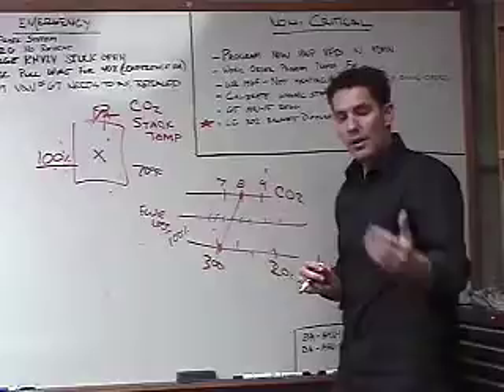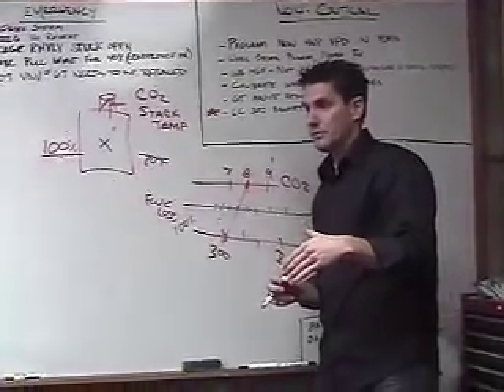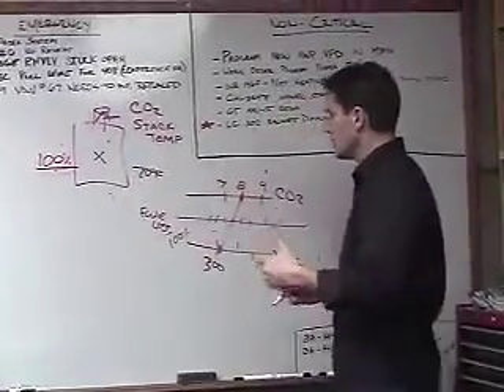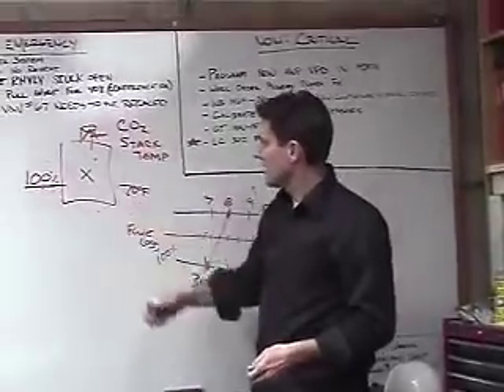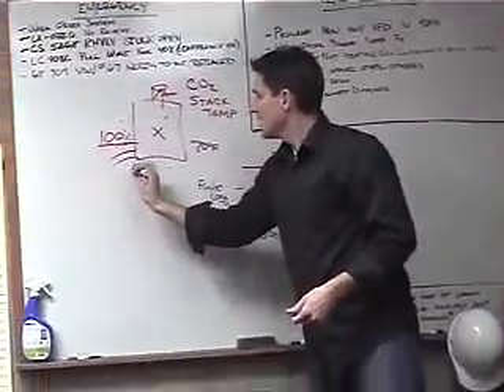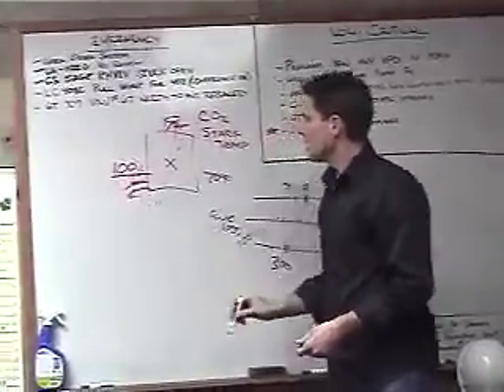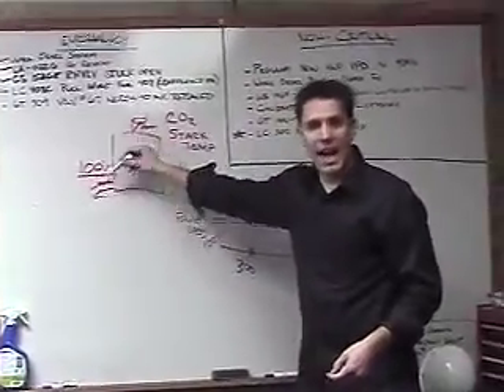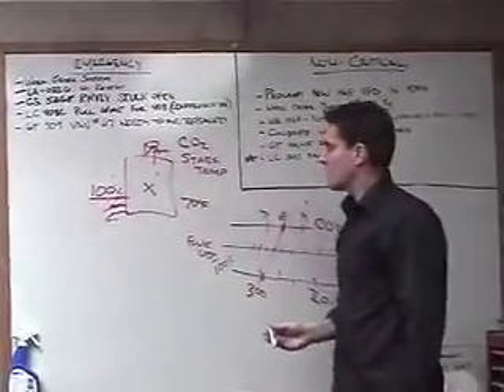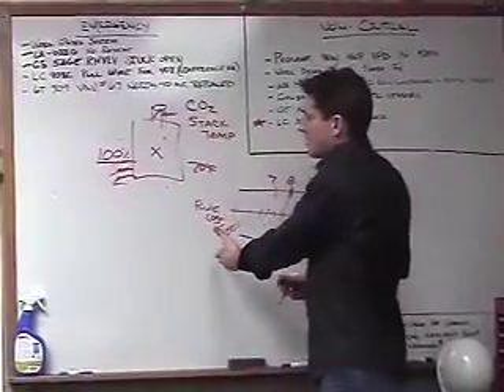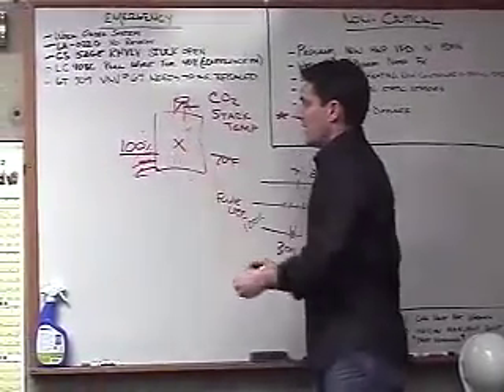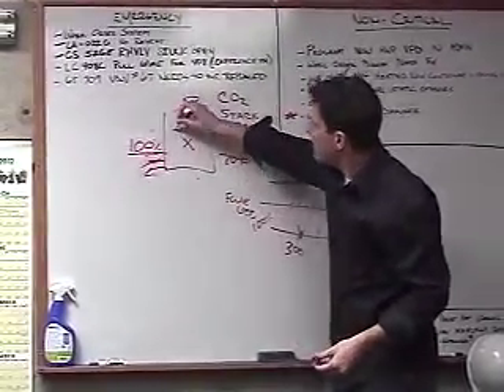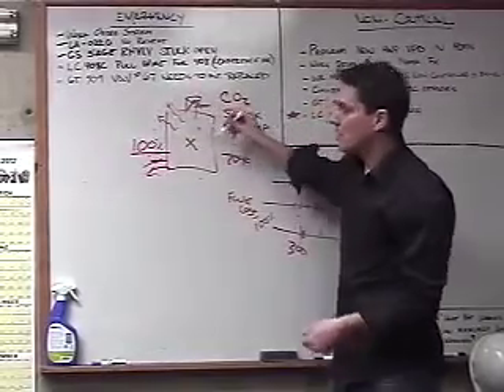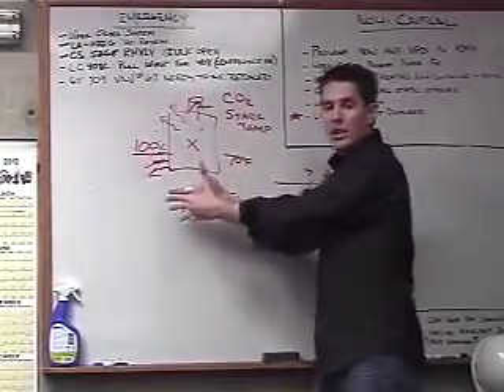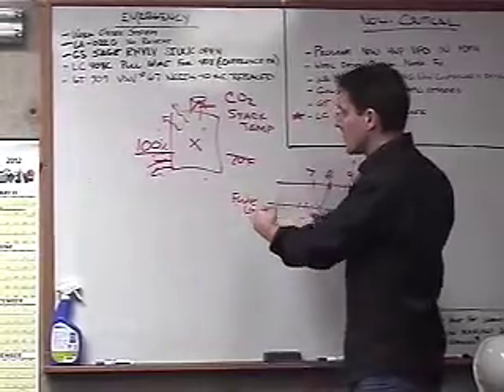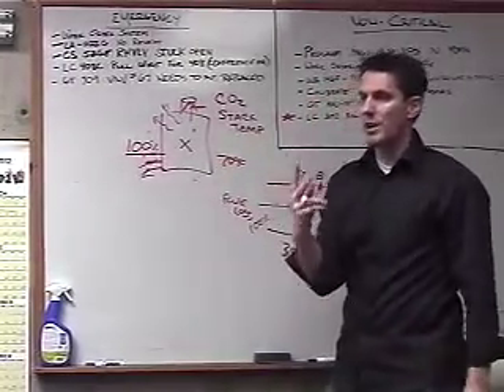That's fine. Have you heard of thermal efficiency? No? Thermal efficiency is another way that ANSI tells you to test these things. What they'll do there is look at the water coming in and the water leaving, and then they measure the amount of heat that you're adding to that liquid. The only difference between combustion efficiency and thermal efficiency is how much of my heat is going through my jacket, how much am I radiating, and how much of that heat is actually going into my water. So thermal efficiency will always be less, but these are giving me two points.